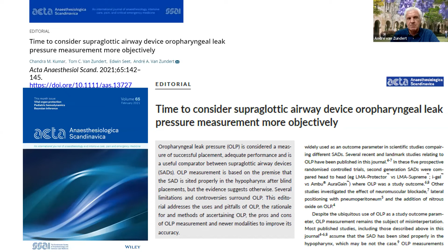Now, the blind insertion technique usually results in malpositioning of the device in 50 to 80% of the time. That means I call that a failed supraglottic airway device. It has been proven over and over by imaging techniques, MRI, CT scan, radiology, ultrasound, clinical research, and fiber optic observation. Nowhere in medicine would this high rate have been acceptable by other disciplines. And no anesthetist would accept a tracheal tube insertion that resulted in a leak with ventilation. So are we using different standards here?